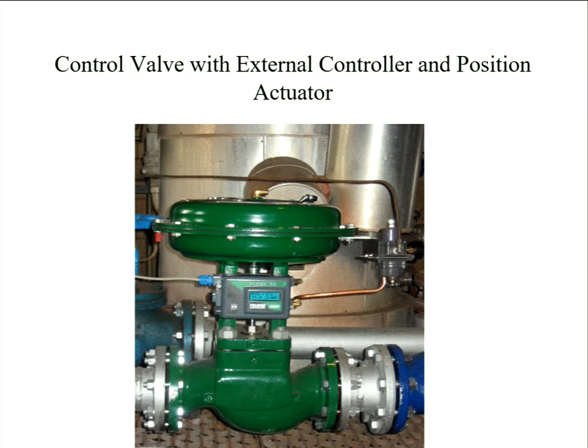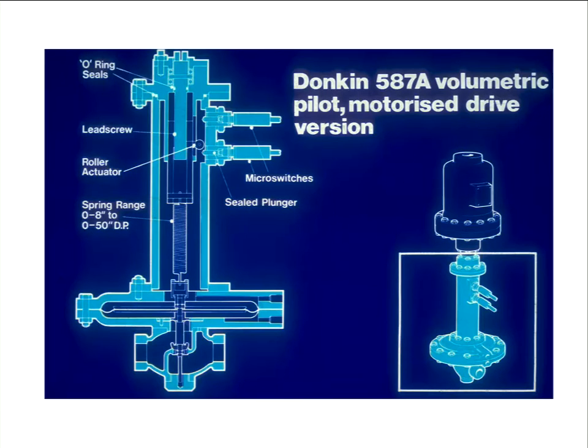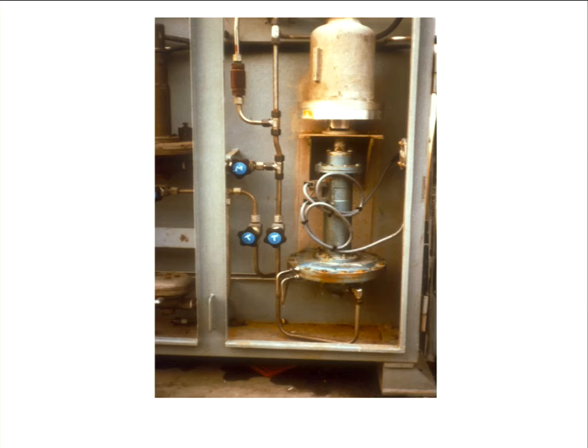Some of this reflects the long history of the UK gas industry, and the fact that stuff was retrofitted onto older equipment. So you're looking at interfaces. If you already had a standard control pilot, a stepper motor that would wind that is probably neater than completely rebuilding that control stream. So this is an example of a control pilot stream, which means that's the flowing stream. The next diagram shows it a little bit better. There's a measurement here that's sampling the pressure, but you can also load the pressure on top of another diaphragm. So you've got an extra diaphragm, pressure load that, and you can achieve remote set point changes.